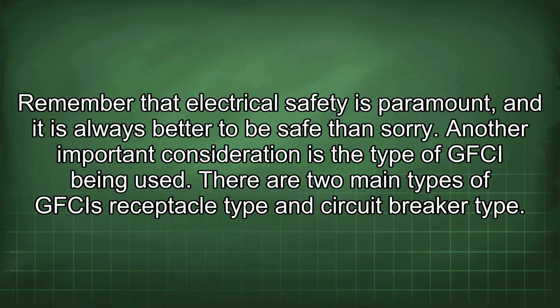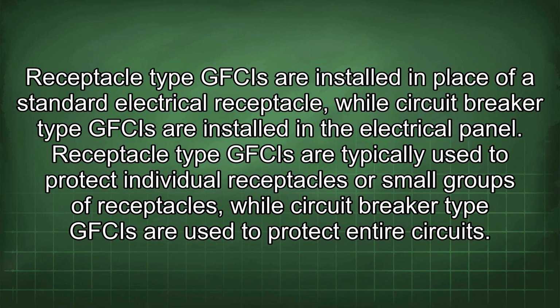Another important consideration is the type of GFCI being used. There are two main types of GFCIs: receptacle type and circuit breaker type. Receptacle type GFCIs are installed in place of a standard electrical receptacle, while circuit breaker type GFCIs are installed in the electrical panel. Receptacle type GFCIs are typically used to protect individual receptacles or small groups of receptacles, while circuit breaker type GFCIs are used to protect entire circuits.